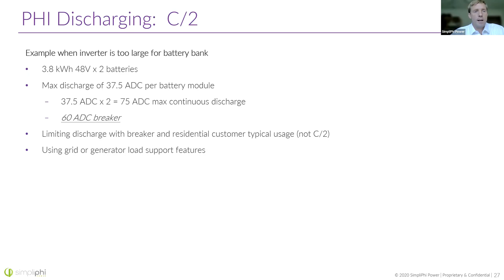So would the breaker work? Well, yes, but here is a graph showing you kind of when a breaker will trip. And so this breaker trips at about 115% of the setting. So this is a 60 amp breaker, but you're going to have to put in more like 80 amps to get this thing to trip.